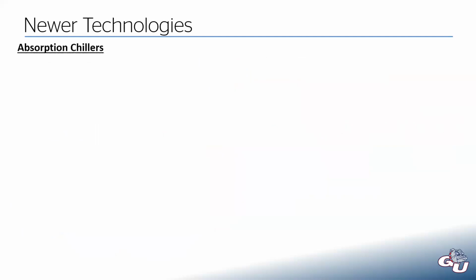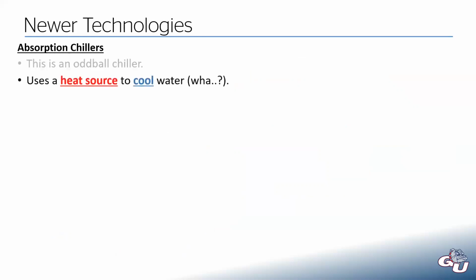And then we have absorption chillers. This is not a new technology. Absorption chillers have been around for a long time, but it is a cool thing that we rarely see. So this is a strange beast. This is an oddball chiller. It uses a heat source to cool water. So it's a chiller, meaning its goal is to produce chilled water, and it does that using a heat source. So that sounds a little odd.